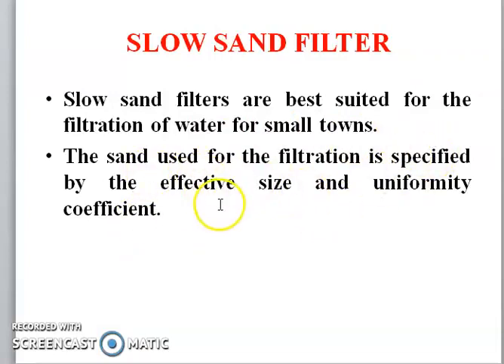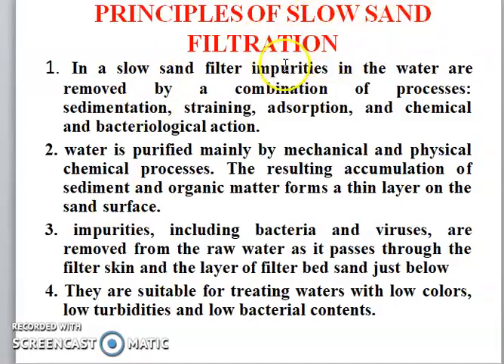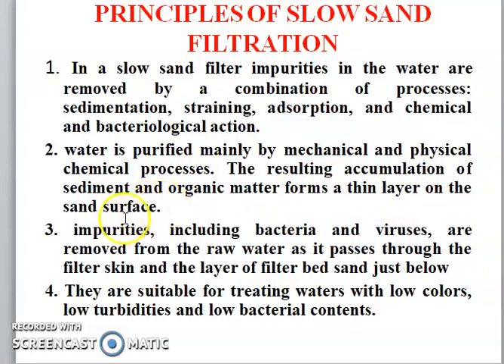The sand used for filtration is characterized by the effective size and uniformity coefficient. In the slow sand filter, impurities in the water are removed by a combination process of sedimentation, straining, adsorption, and chemical and bacterial action. Water is purified mainly by mechanical, physical, and chemical processes. The resulting accumulation of sediment and organic matter forms a thin layer on the sand surface. Impurities including bacteria and viruses are removed from the raw water as it passes through the filter skin layer and the filter bed sand just below. They are suitable for treating water with low color, low turbidity, and low bacterial content.